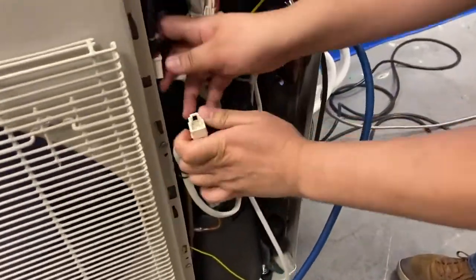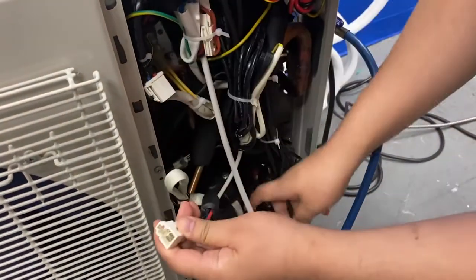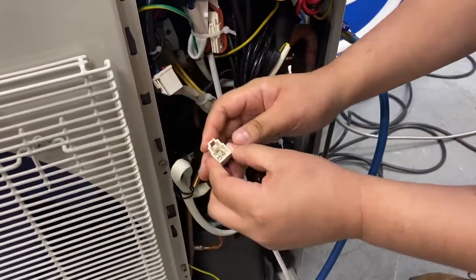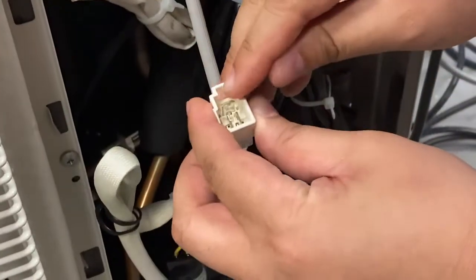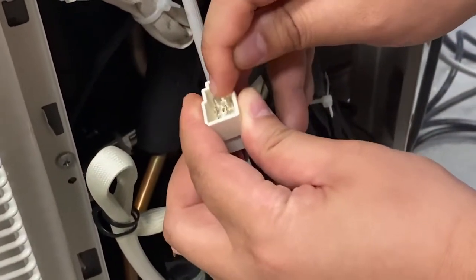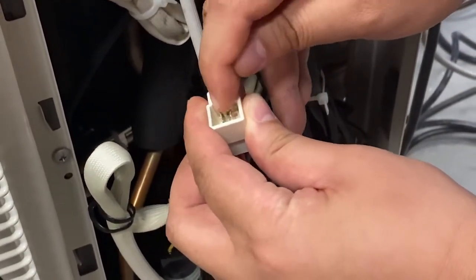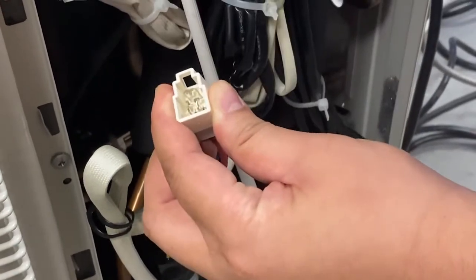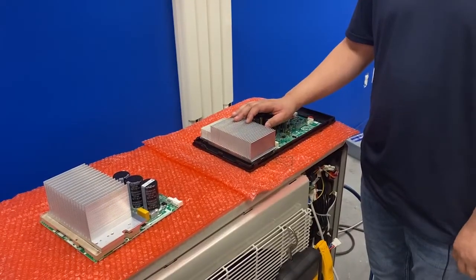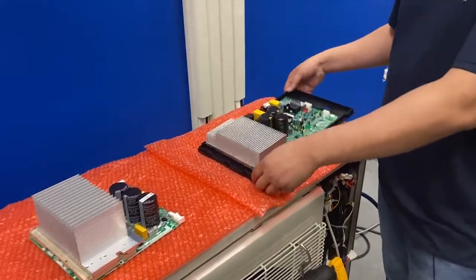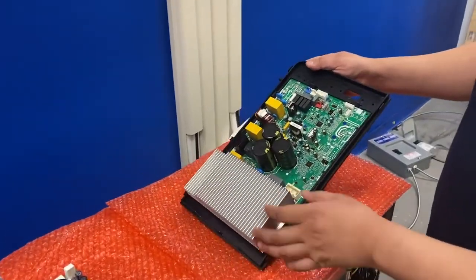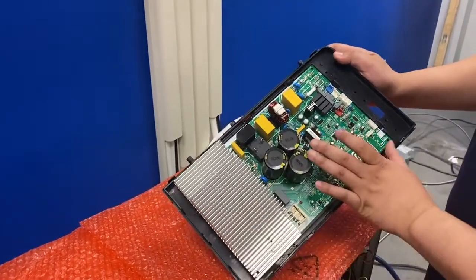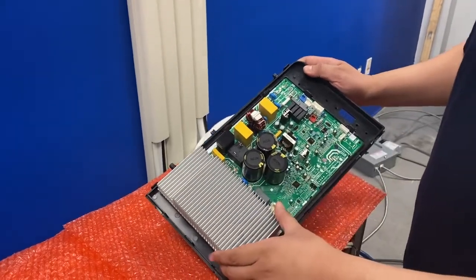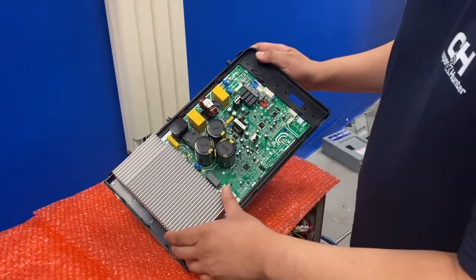Here I have unplugged the compressor from the main control board. We're going to check resistance values between the 3 pins, between 1 and 2, 1 and 3, and 2 and 3. Here I have 2 examples of IPM boards. This one is an IPM fused with the main control board, and generally you'll see this set up on our smaller BTU units.